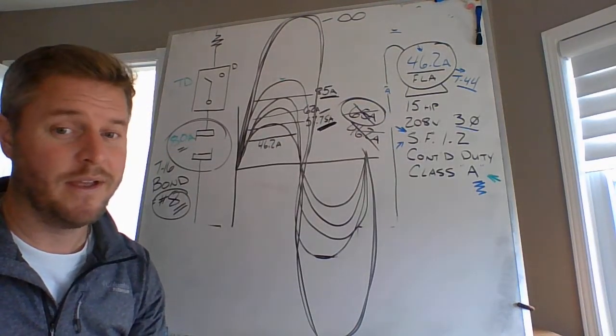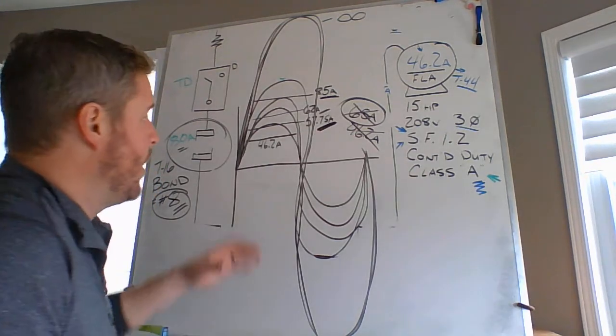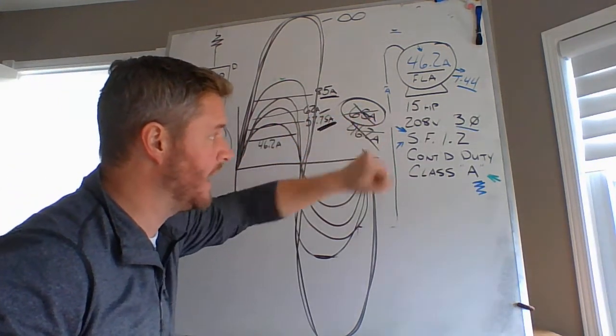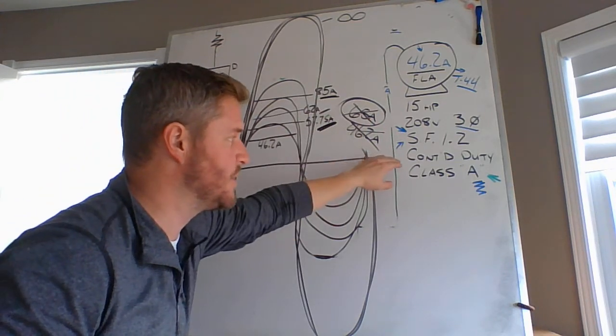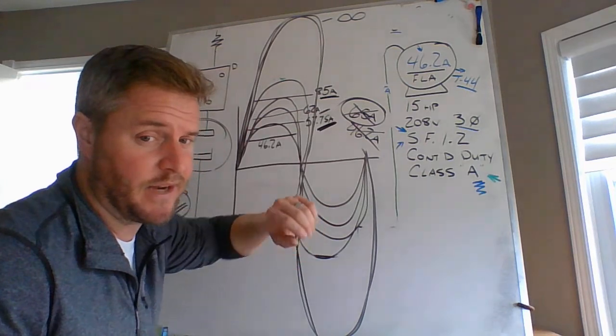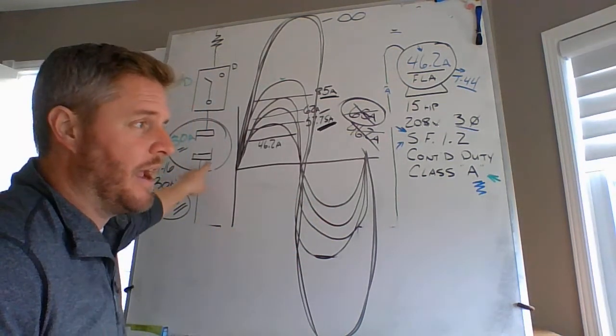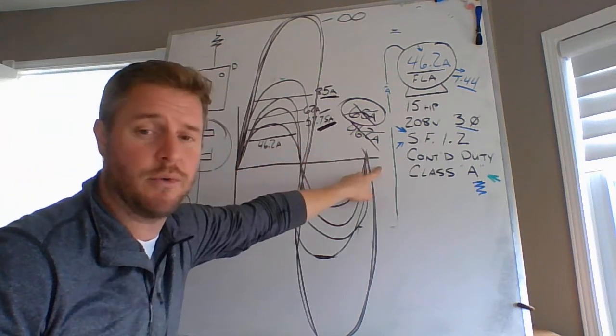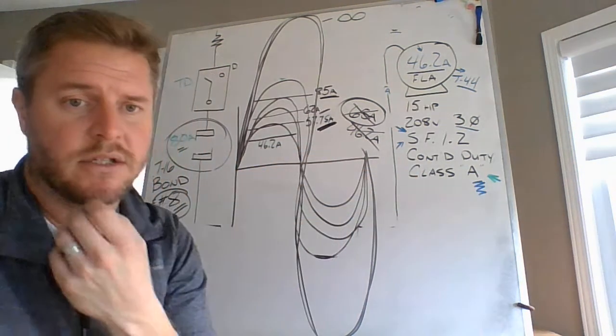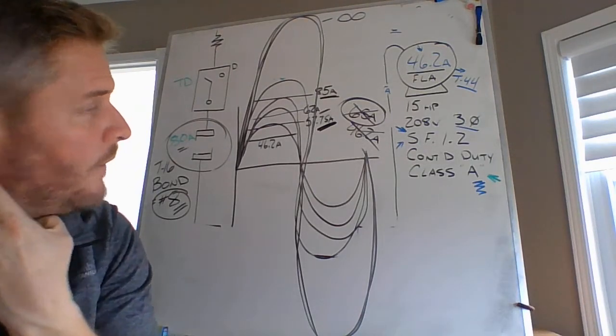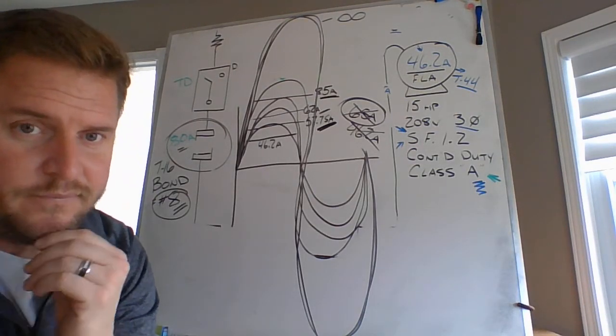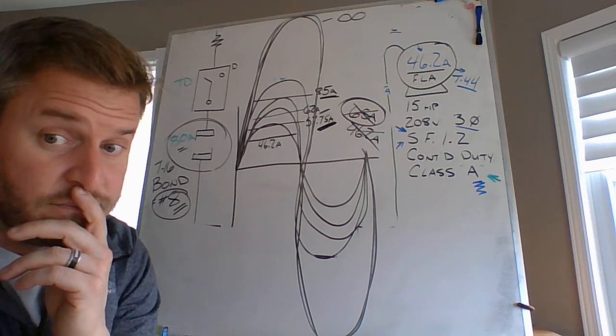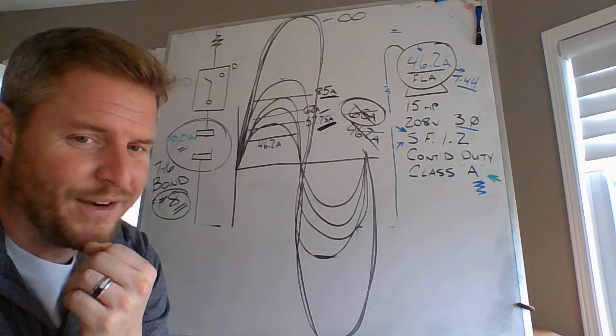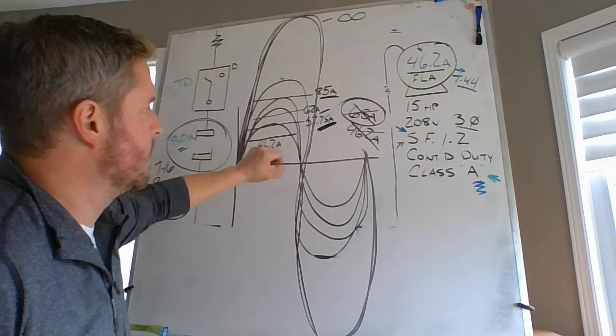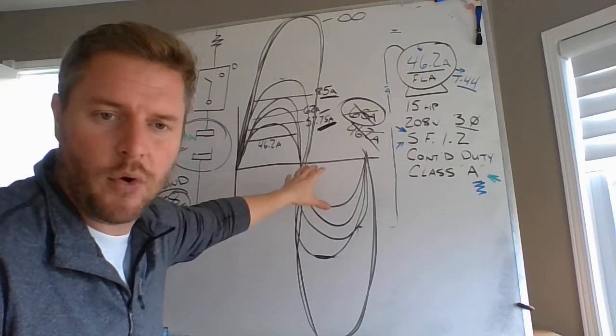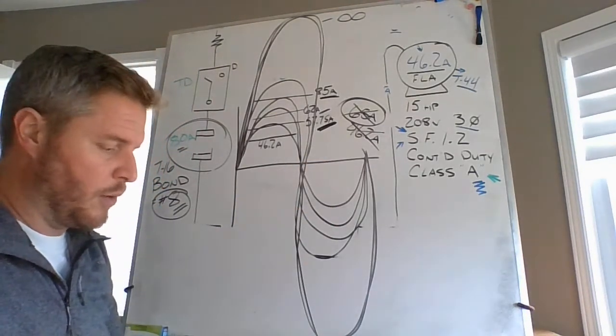Kind of cool, right? So, a prime example of how your overcurrent devices are actually operating in a circuit based on a continuous duty Class A motor. The difference between your overload protection and your overcurrent protection based on the conductors that you install for this 46.2 amp full load current rating of the motor. That's fun, right? There's a little bit of instrumentation, there's a little bit of electronics, there's a little bit of theory, there's a whole bunch of code for you to study for that specific motor.